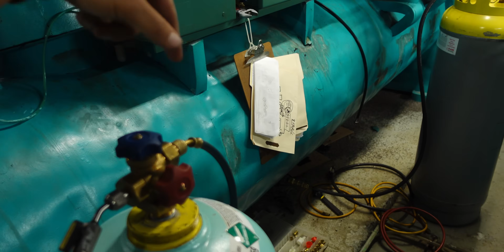I didn't point it out, but we started at about 9:10, 9:15, so we're essentially 15-20 minutes-ish into it. Once we actually pump all the liquid through, we will then stop. We will reconfigure the hoses, and then we will do a vapor pull on all of this instead, and that'll finish off the recovery. We'll finish off the last bit via vapor. And one of the issues you have is with these tanks, none of them will you actually get all the liquid. You will still have a little bit of liquid because those pickup tubes stick up a couple of inches off the bottom of the tank itself.